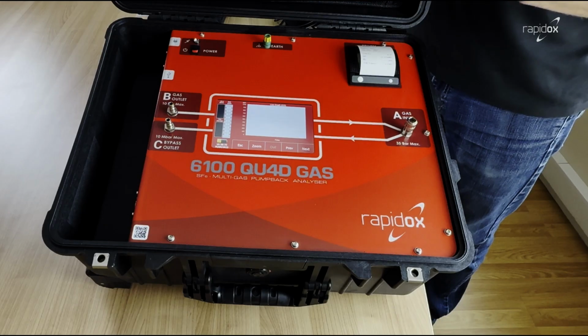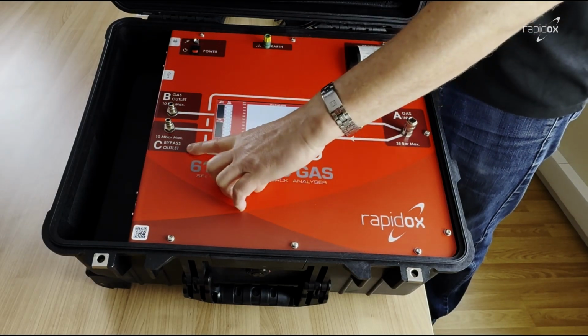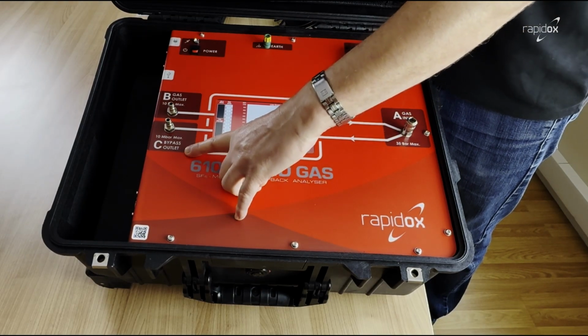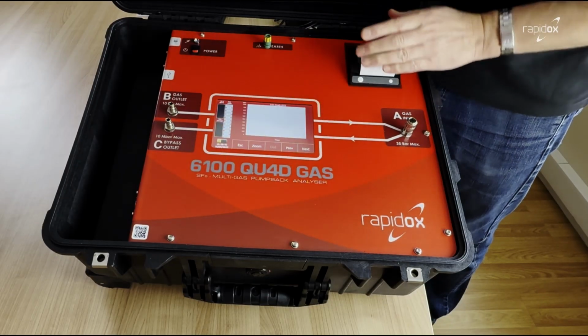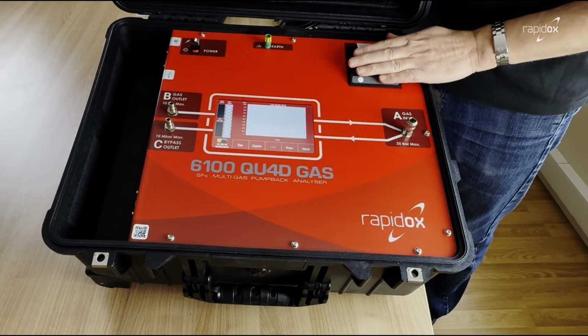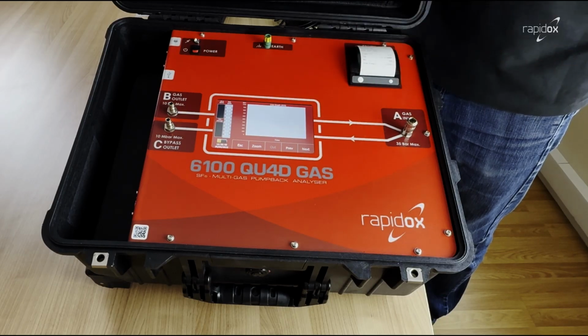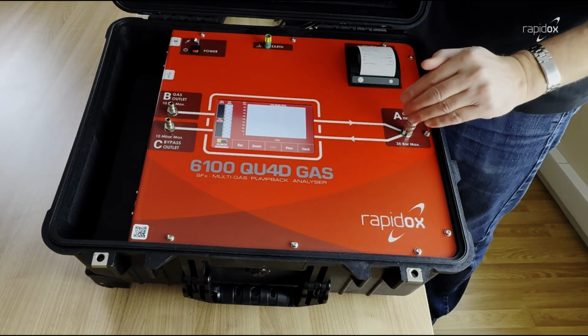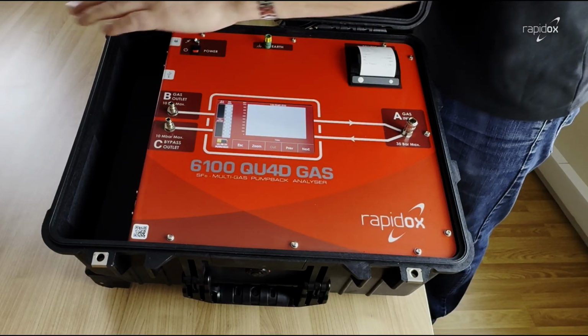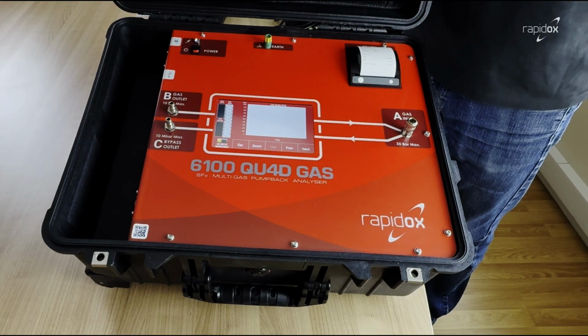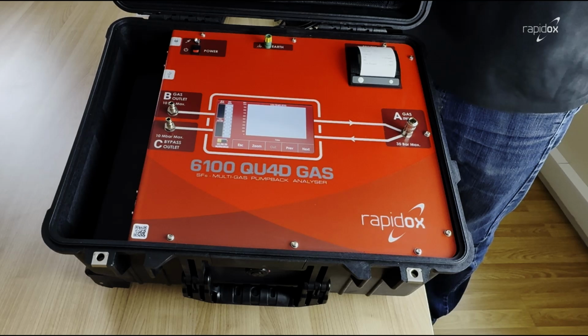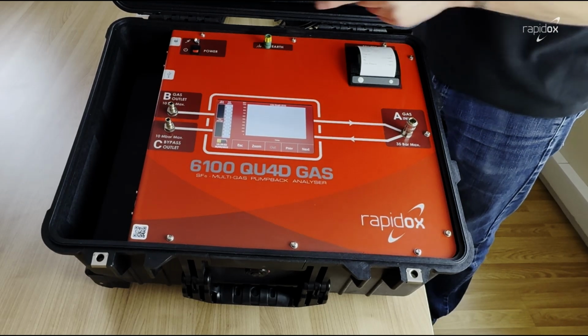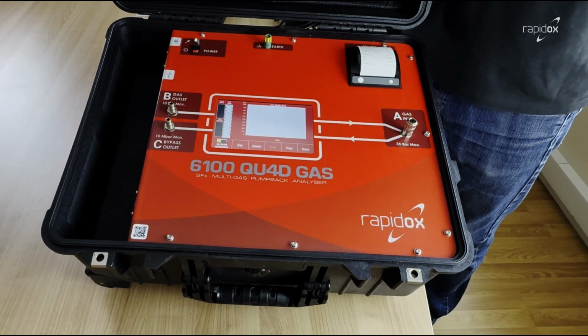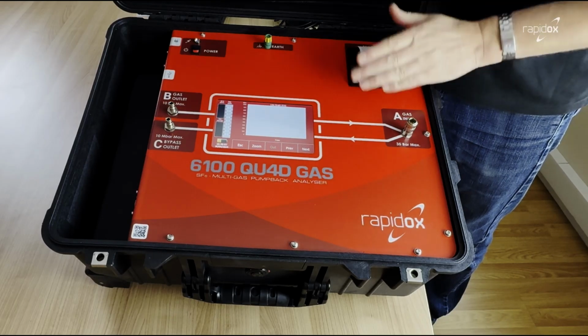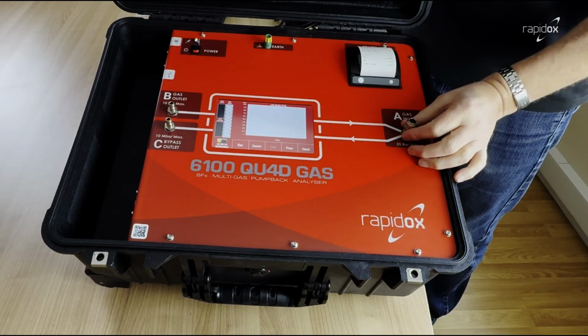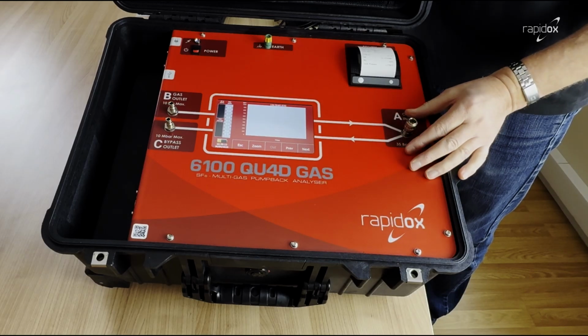And then finally we have port C, which is not really used very often. It's called a bypass port. Now port C is used primarily for calibration purposes. It can also allow the analyzer to run in a continuous mode where the gas goes in here at port A and comes out in port C. But normally, for most people, it's used for calibration. It's used for testing the dew point sensor over extended periods of time where we have to have a lot of nitrogen flowing through the analyzer to do calibrations. So for most people, most of the time, only port A is used to keep things simple.